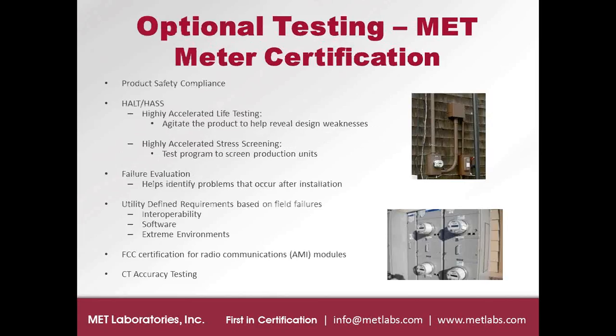Okay, thanks, Monty. That is the overview of our ANSI Meter Certification Program in terms of the ANSI C12 testing for accuracy, the EMCs, the environmental tests. We do have optional test programs that may be useful as well, and here's a glance at some of those. As I said, we're an NRTL for the product safety compliance program. We do offer HALT and HASS testing, the highly accelerated life testing in particular we perform here. The stress screening program is normally something that's done on the production units at the manufacturer, but we could offer that as well and certainly offer guidance toward it.